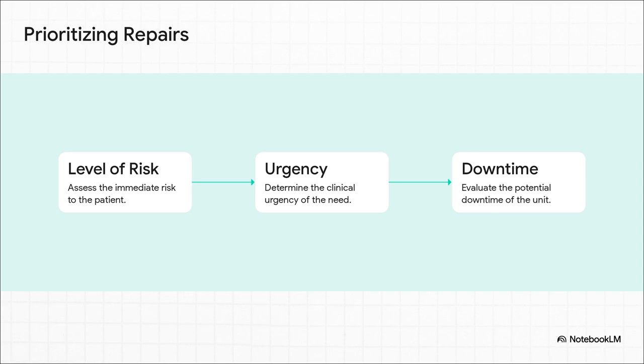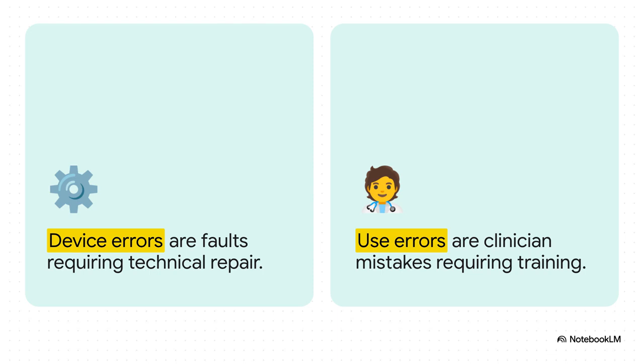A sudden ICU equipment failure is always going to take priority over a routine preventative maintenance check. You've got to be able to handle that pressure and make the right call instantly. Here is another totally essential distinction for troubleshooting: device errors versus use errors. Device errors are actual mechanical or software faults in diagnostic or therapeutic equipment that require your technical, hands-on repair. But use errors? Those are clinician mistakes, like when a nurse says a device is broken, but they just haven't tried turning it off and on again. That's a use error. BMETs play a vital role here by leading clinical staff tutorials to ensure proper use and drastically reduce those kinds of occurrences.